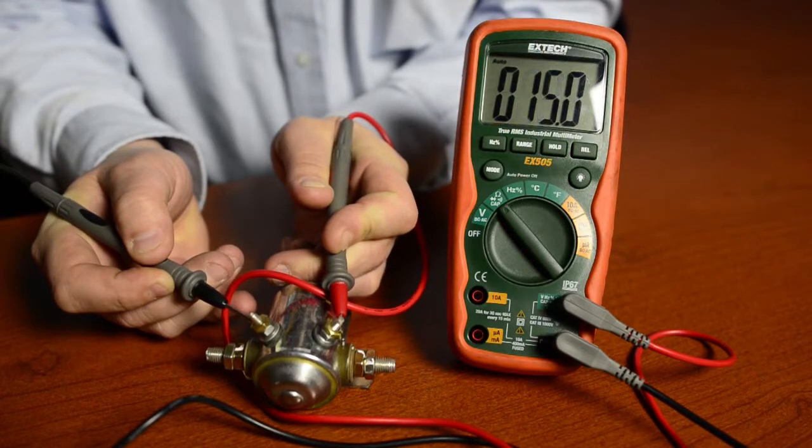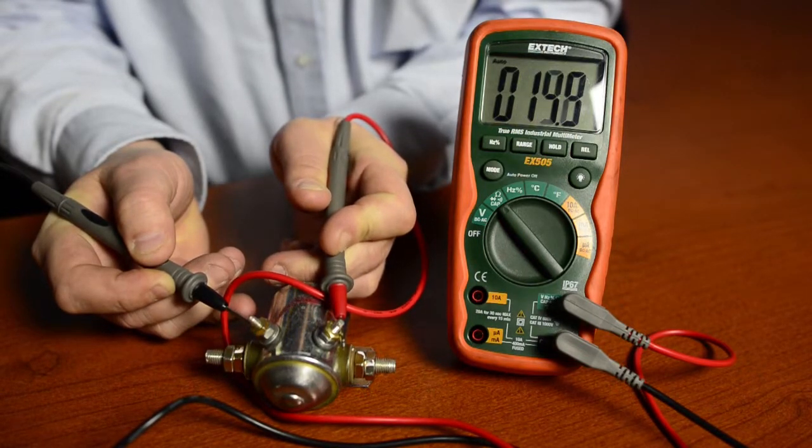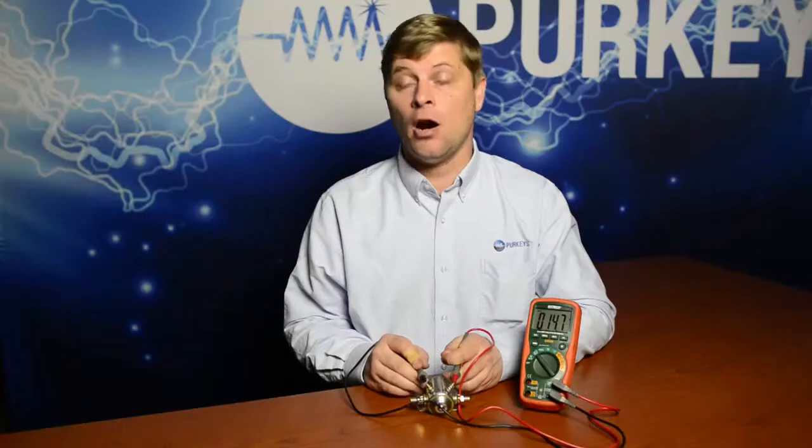Right now we have a resistance of about 14.8 ohms. Are we done? No. The other part of this is we have to go back to our manufacturer's specifications and see if that is a good reading for this particular part.